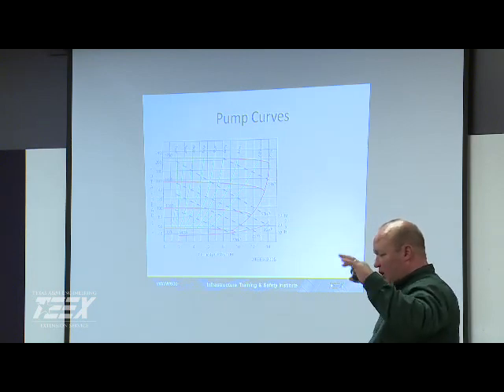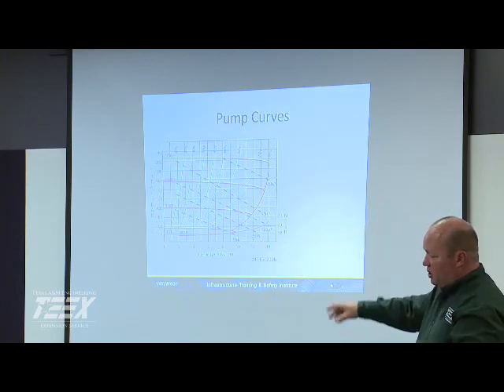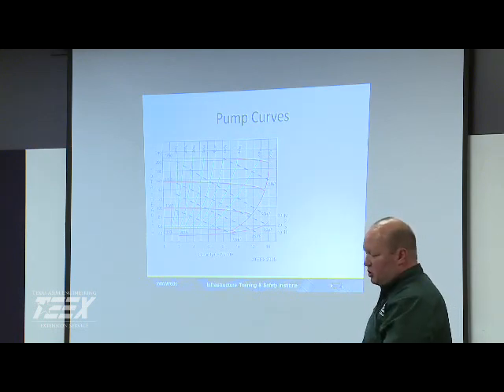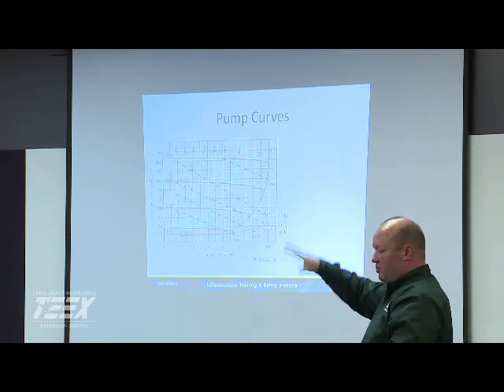So you're looking at your total dynamic head. How much do I have to push against? How much am I trying to push? If I try to push a lot of water a long way, I need a lot bigger motor, and my efficiency is going to drop off. And then the NPSH is your net positive suction head. How much do I actually need pushing down to be able to meet that requirement?